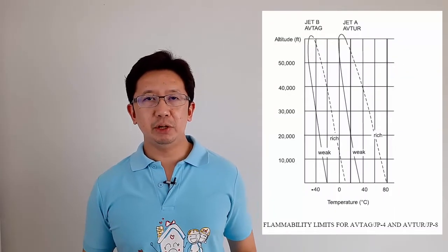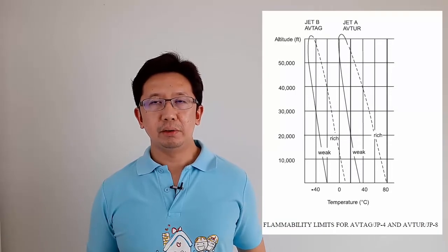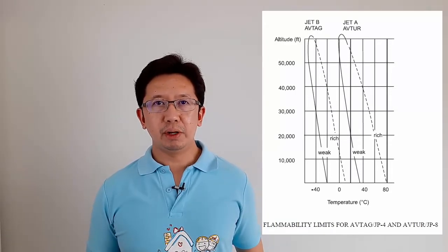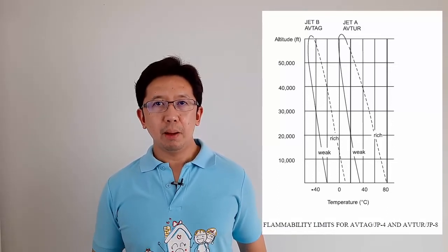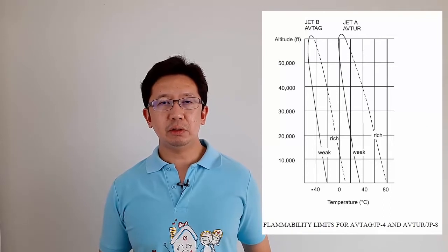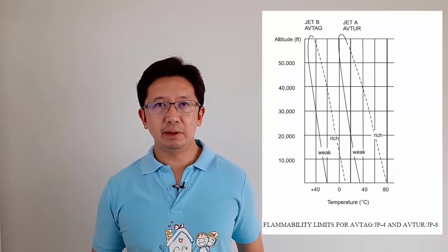Compared with Jet A, Jet B is a more serious practical hazard under normal temperature conditions, since the Jet B flash point ranges between minus 23 degrees Celsius and just 27 degrees Celsius. The preferred jet fuel storage tank of the FAA, or Federal Aviation Administration, is the above ground type, called above ground storage tank or AST, to reduce environmental liability. Leakage of an underground storage tank poses a significant threat to the environment.